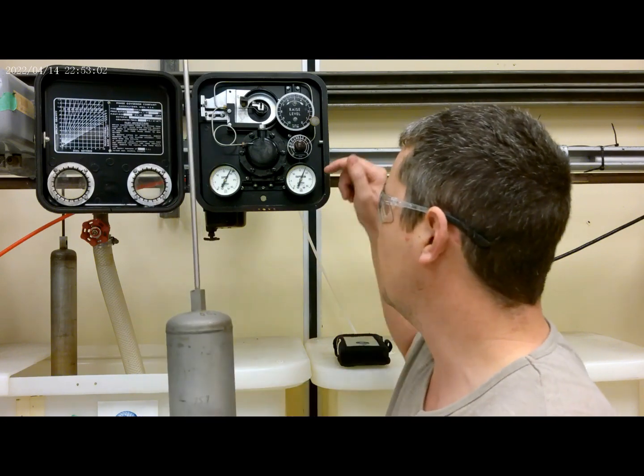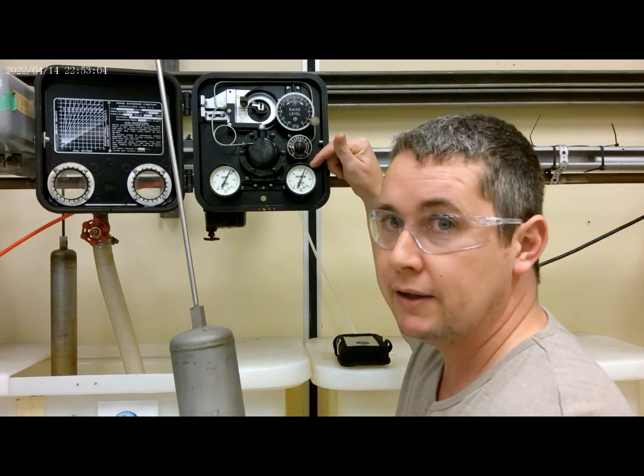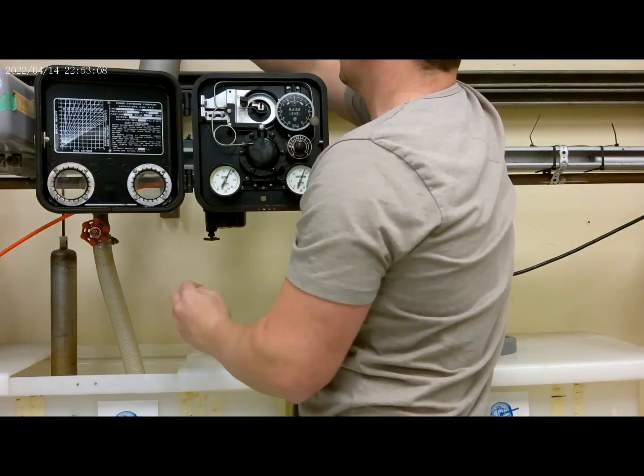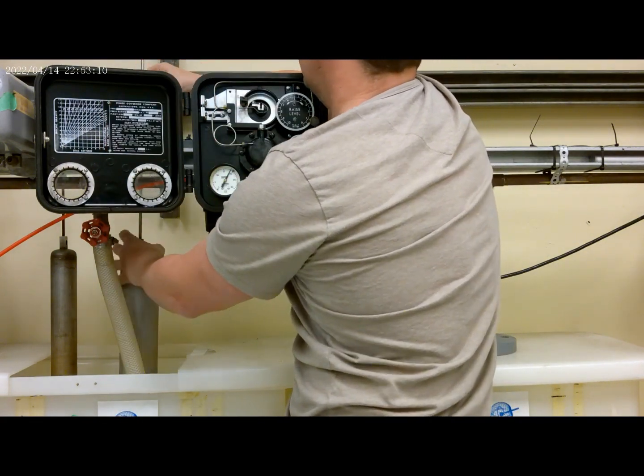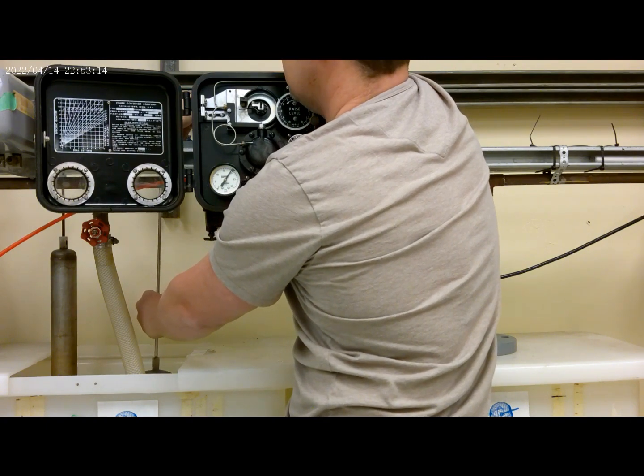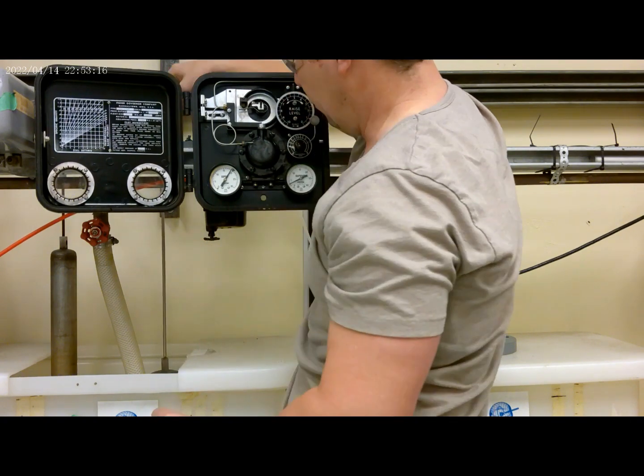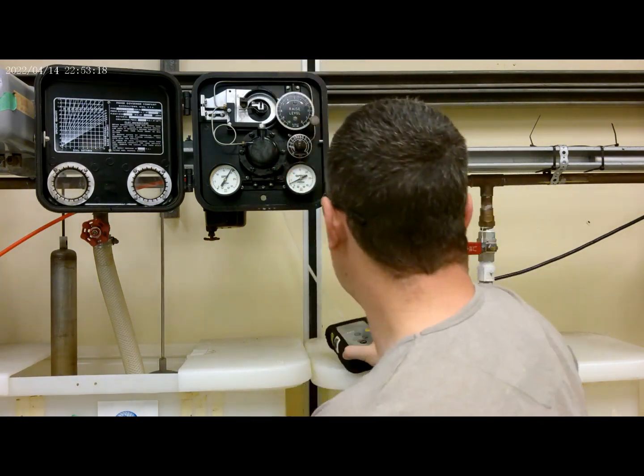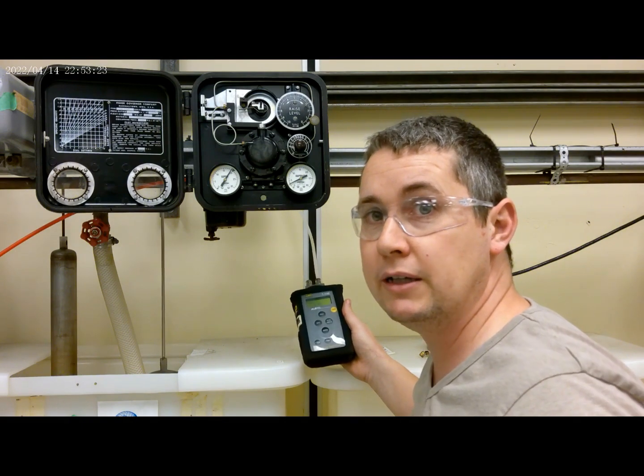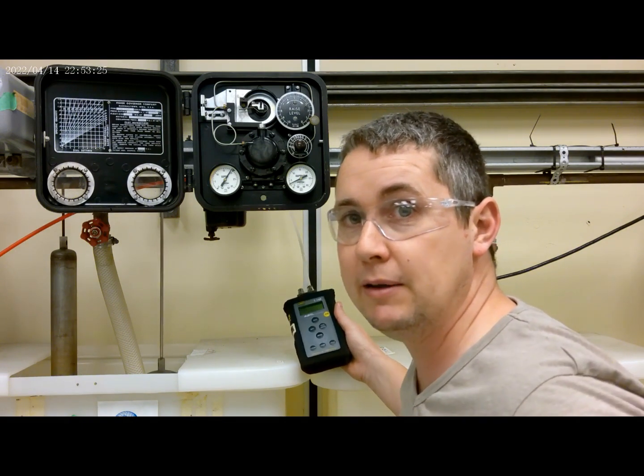Notice that as I took this off, it went to 100% output. That's because there's no weight on it currently. So now, I put my displacer back in the tube, put it back on the rod. I am at 0% currently, and I am getting 3 psi. I'm going to zoom in so that you can see this better. You're not going to see me, but you'll be able to see all the numbers and everything better.